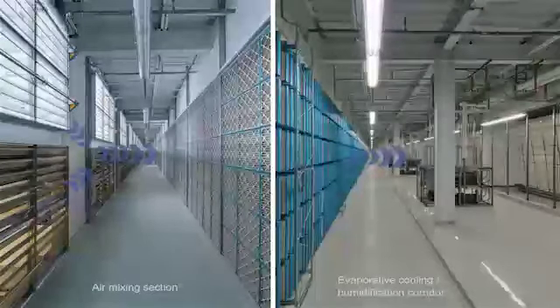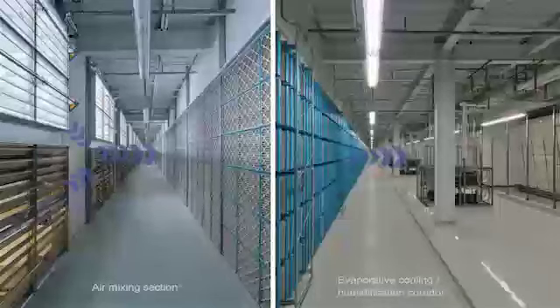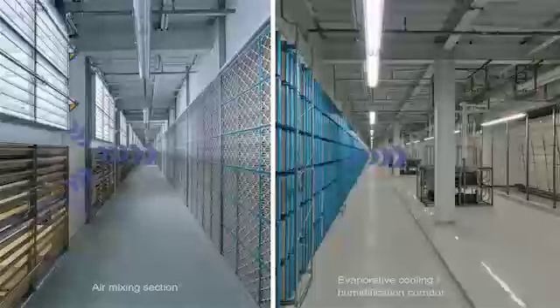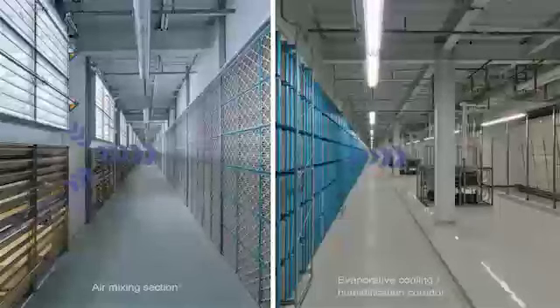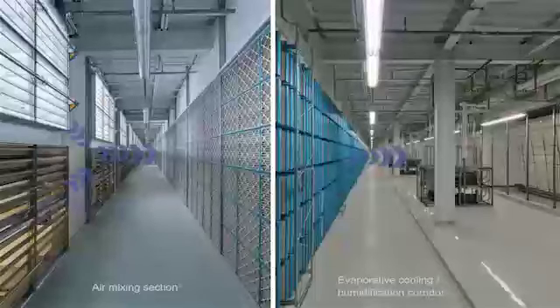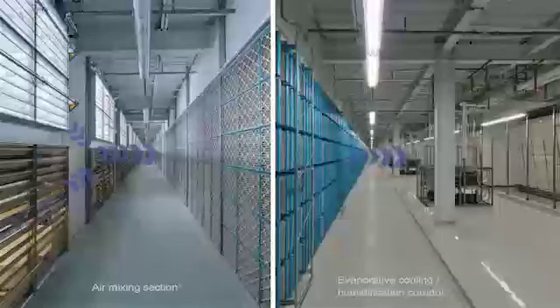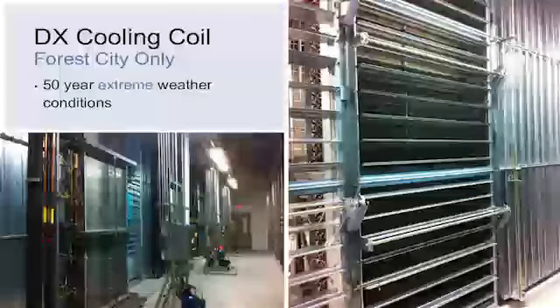We have our filter corridor, our mixing area. The bottom louvers are our return heat from our data center. We come through the filter wall, and this is the galley area that is reserved for the introduction of condensing coils or condenser water loop. Moving along, these are the DX coils that we installed in Forest City with bypass dampers. So in the event we don't need to use the DX system, we're just bypassing all the air to minimize the amount of pressure loss.